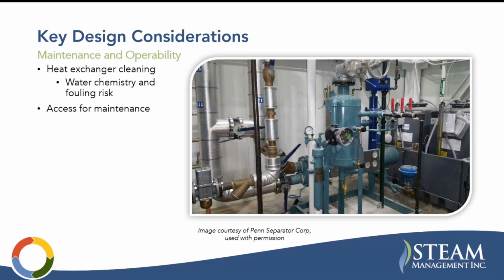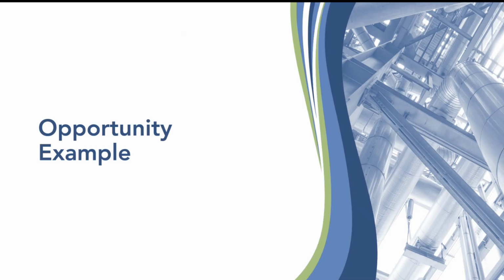Some other design considerations like maintenance and operability. I would say heat exchanger cleaning. So if you think about it, this is dirty blowdown water being used in your heat exchanger, it is going to eventually need to be cleaned, and you need access for that. So that's always something to think about on these.